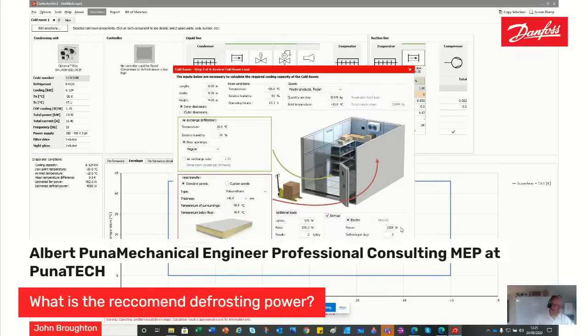What I would always say whenever doing a selection in something like this is, once you've done the selection and you've selected your evaporator, just double check the actual size of the defrost heaters in that evaporator, to make sure that this figure here, this 5,268 watts or 5.2 kilowatts, is there or thereabouts what you've actually got in your evaporator. There are calculations, and I've got quite a few books around my office that give me the approximate defrosting power per size of evaporator at different conditions. So that information is available, but it is taken care of within Coolselector, but just do a double check on that.